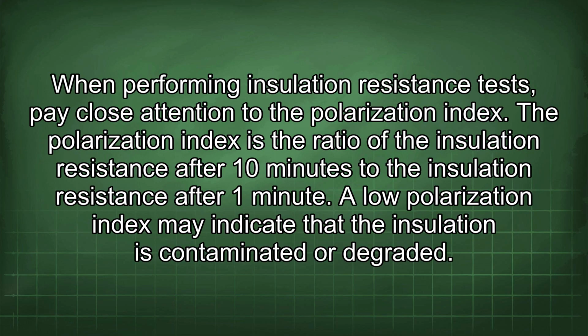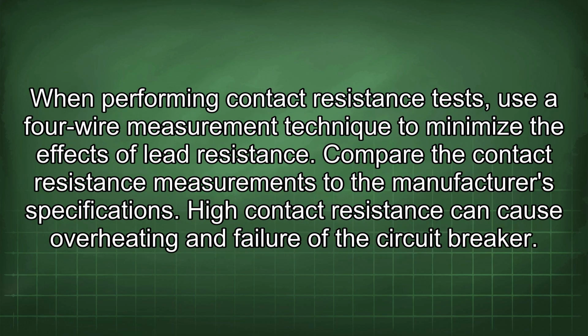When performing insulation resistance tests, pay close attention to the polarization index. The polarization index is the ratio of the insulation resistance after 10 minutes to the insulation resistance after 1 minute. A low polarization index may indicate that the insulation is contaminated or degraded. When performing contact resistance tests, use a four-wire measurement technique to minimize the effects of lead resistance. Compare the contact resistance measurements to the manufacturer's specifications. High contact resistance can cause overheating and failure of the circuit breaker.